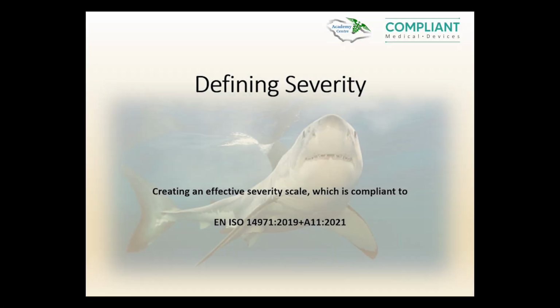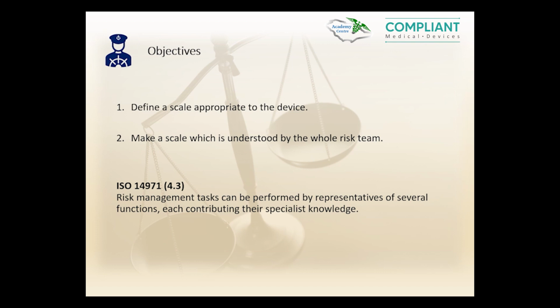The topic for today is to explore a procedural approach in defining the severity scale for risk management. Defining severity: creating an effective scale which is compliant to ISO 14971, the risk standard. We need to define a scale which is appropriate to the device, and the scale needs to be understood by the whole risk team.